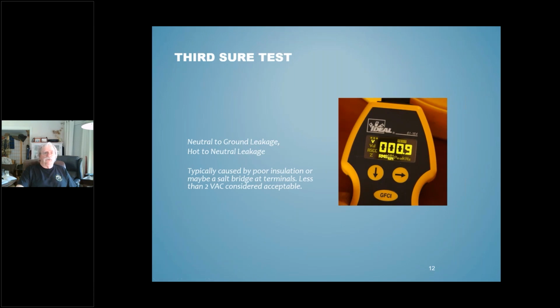The next test is neutral to ground leakage and hot to neutral leakage, typically caused by either a bad installation or insulation rather, or maybe a salt bridge at some terminals. According to Ideal, less than 2 volts AC is considered acceptable. So here we see 0.9. I don't remember where I was testing it, quite frankly, and where I got that reading. But don't be surprised if you get a low-level reading like that. It's not cause for great concern.